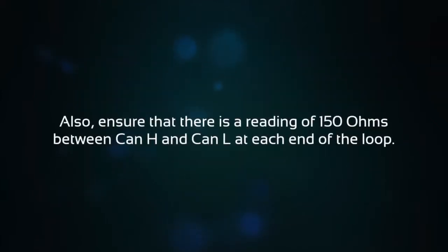Also ensure there is a reading of 150 ohms between CAN H and CAN L at each end of the loop.